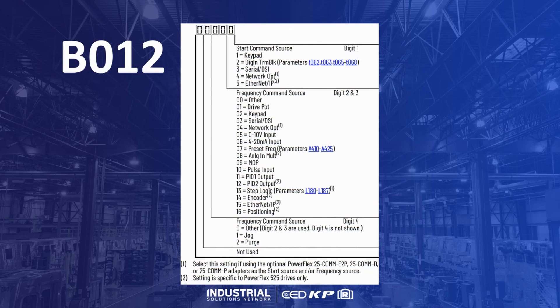Skipping ahead, parameter B12 will indicate both the frequency command and start source for the drive. Starting from the left, the first digit of parameter B12 indicates the control source, such as the keypad or Ethernet connection. The next two digits indicate the frequency reference, while the fourth digit is present when the frequency source is either jogged or purged.